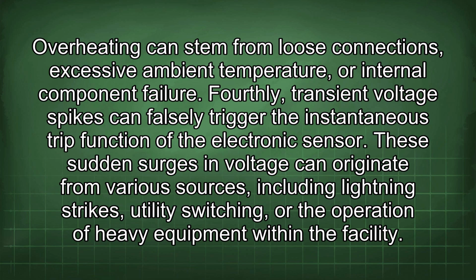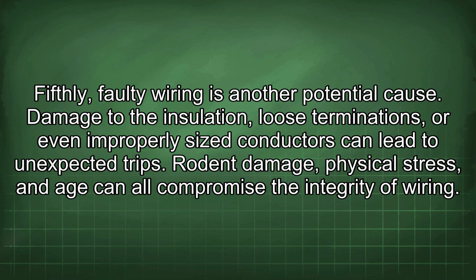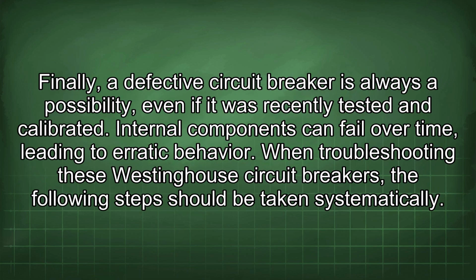Fourthly, transient voltage spikes can falsely trigger the instantaneous trip function of the electronic sensor. These sudden surges in voltage can originate from various sources, including lightning strikes, utility switching, or the operation of heavy equipment within the facility. Fifthly, faulty wiring is another potential cause. Damage to the insulation, loose terminations, or even improperly sized conductors can lead to unexpected trips. Rodent damage, physical stress, and age can all compromise the integrity of wiring. Finally, a defective circuit breaker is always a possibility, even if it was recently tested and calibrated. Internal components can fail over time, leading to erratic behavior.